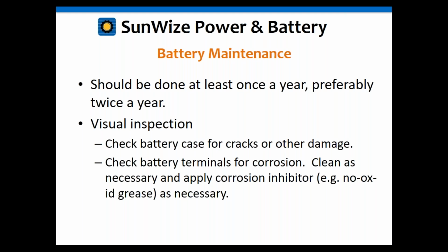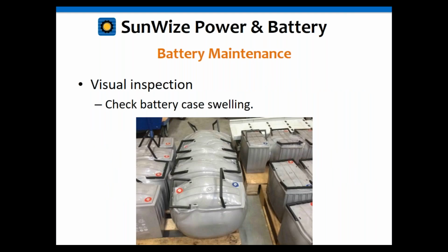We want to start with a visual inspection. We want to check batteries for any cracks or other damage. Check terminals for corrosion and clean as necessary. You can also apply a corrosion inhibitor like a No-Ox-Id grease or something like that to help minimize corrosion on connections. And this is an example of batteries that have swelled.